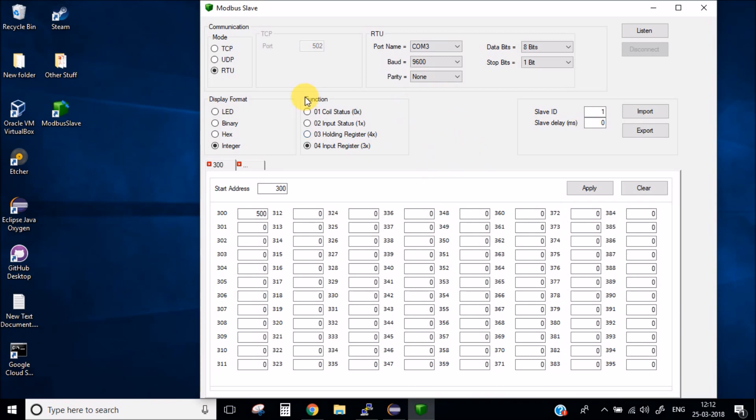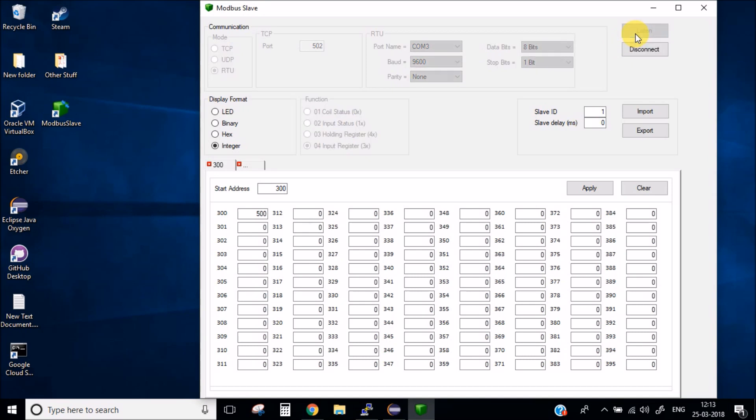I have connected a Modbus dongle in my laptop. The mode which we will be using is RTU mode and these are all the properties. Let's click this listen button. Now here you can set all the values you want to set in the registers of the Modbus. For example we will be using this 300 register and let's set the value of it to 500 and simply click apply.